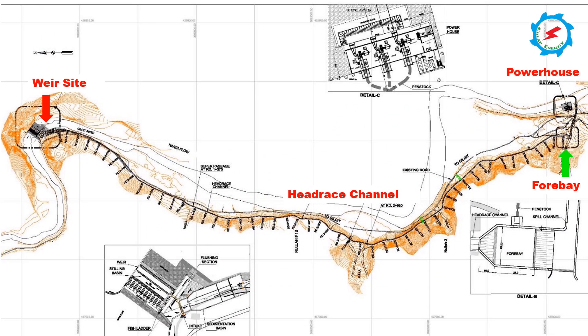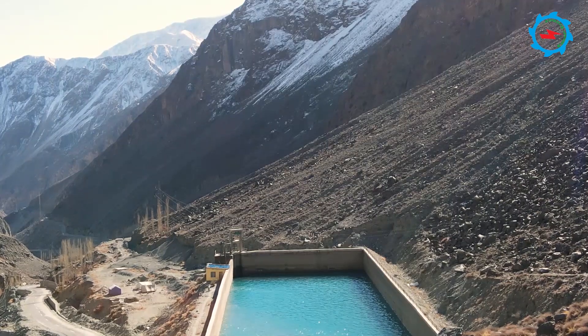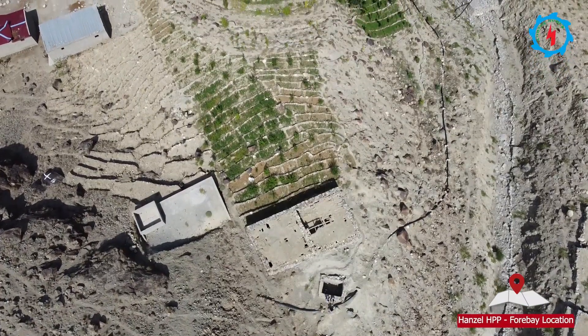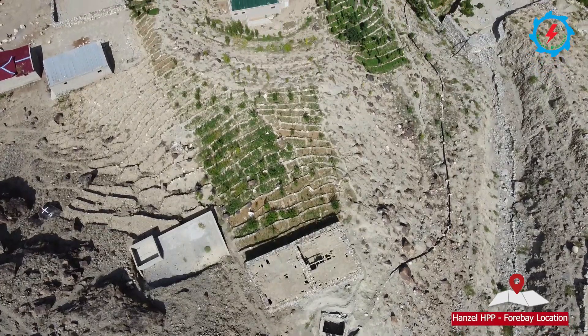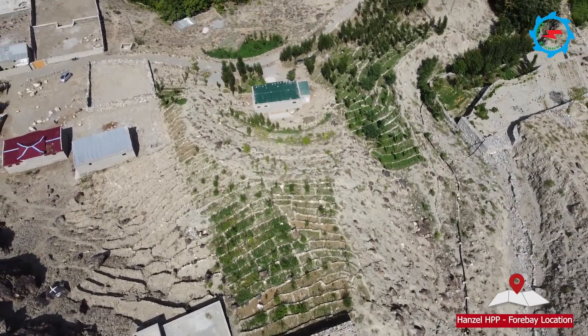The forebay structure as planned will be of pond type, having a length of 25 meters and 25 meters wide, with a spill weir over the right wall which leads water into a spill channel. Three steel penstocks of 1.75 meters diameter and 231 meters length have been provided.